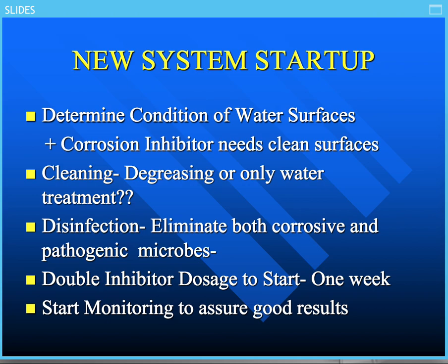Yes, you do. If it's mild steel, you have to make sure that the corrosion inhibitor can get to those surfaces. That means it's got to be clean. If it's dirty, on a new startup system, a new system may have just oils and greases and a little bit of rust. But don't assume that that's all it has. It could have a lot more corrosion that requires not only cleaning by degreasing or using water treatment, or it could require a more strenuous type of cleaning program, just to make sure you got the surfaces clean, so that you actually can allow the corrosion inhibitor to get into those metal surfaces and stop the corrosion that may occur due to the corrosivity of the cooling water.